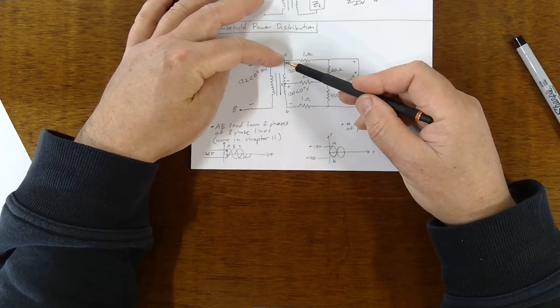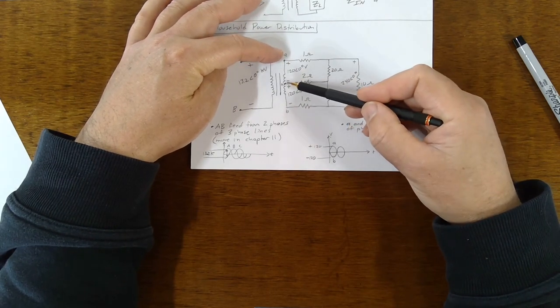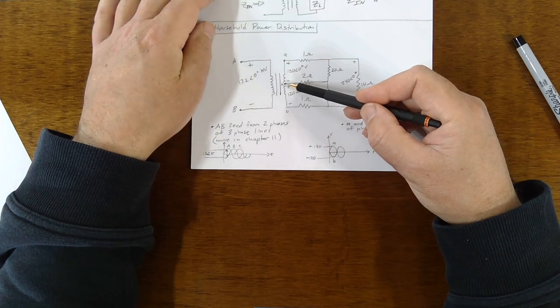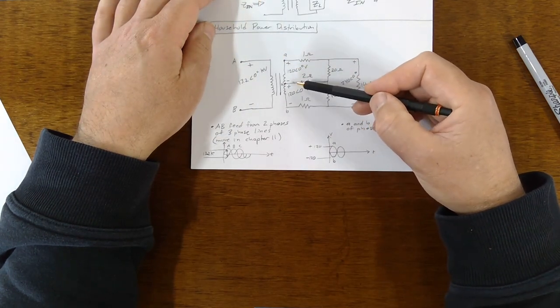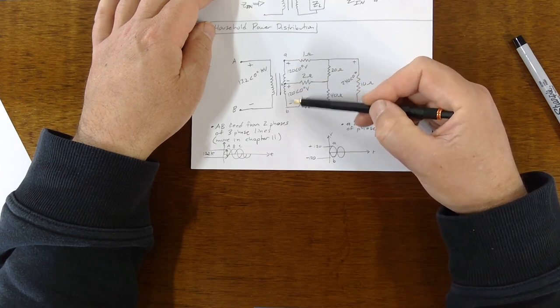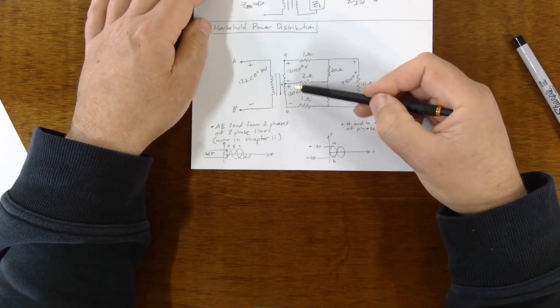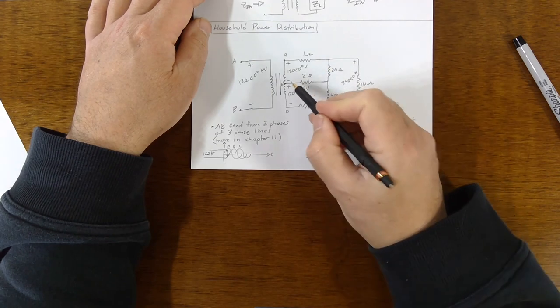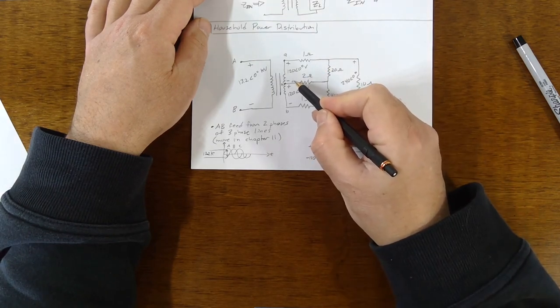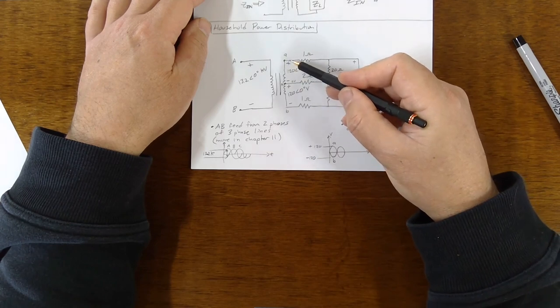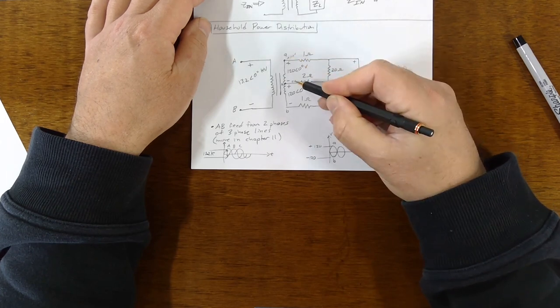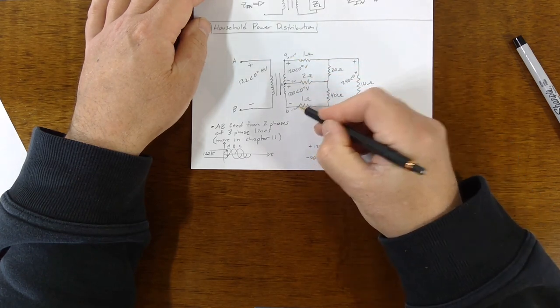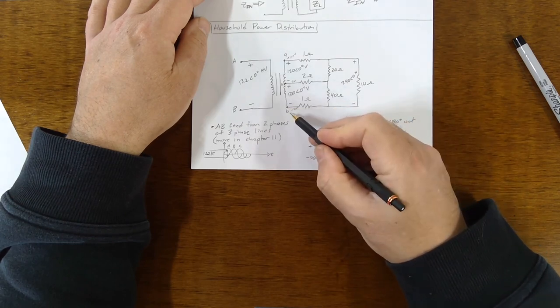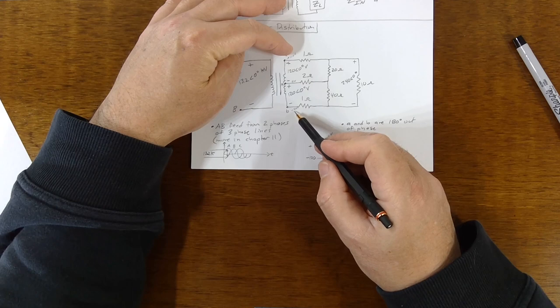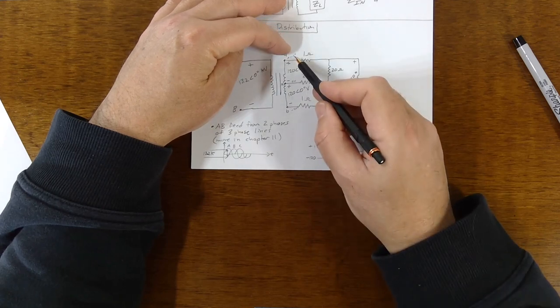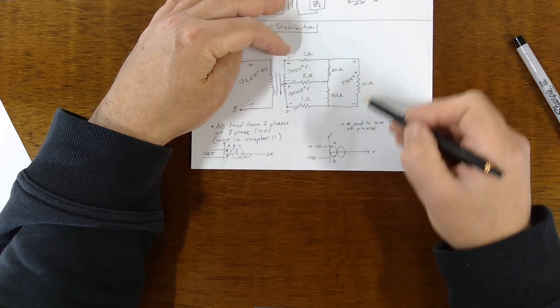Okay, so you've got A and B nodes, little A and little B nodes here, from neutral, which is grounded, the center tap, to A. That's 120 volts with this polarity. And then from neutral to B is this 120 volts with this polarity relationship. It's minus plus, minus plus. So it's 0 volts here because it's grounded, and it's positive 120 here, so it'd be plus 120. It's 0 volts here and then it's dropping 120, so it's minus 120 volts at little B node. So that means that from this positive 120 to this minus 120 is 240.